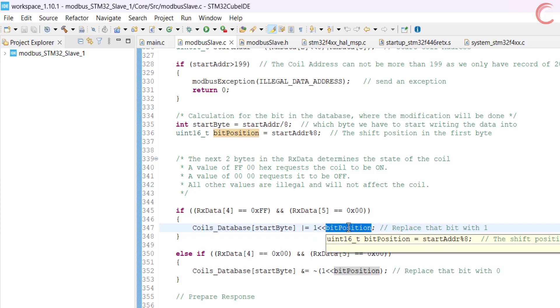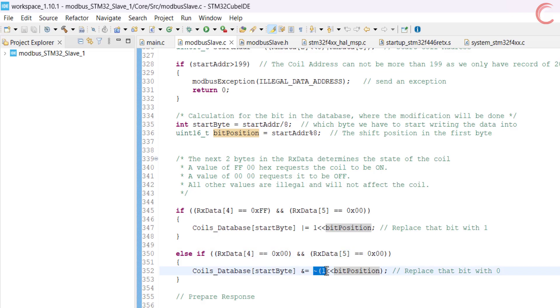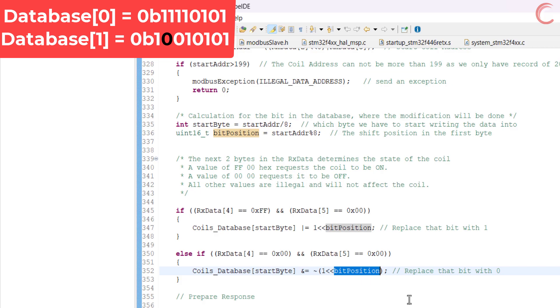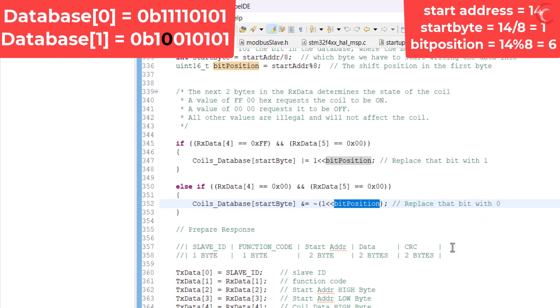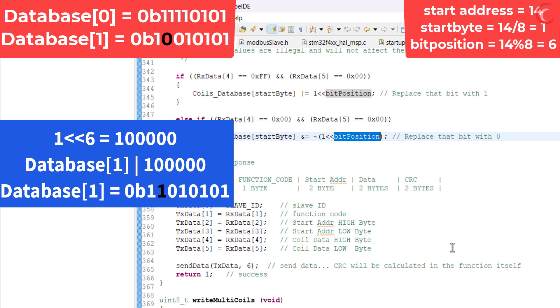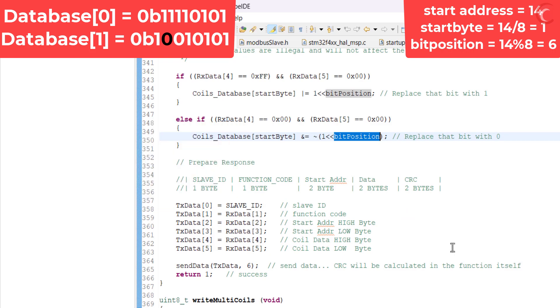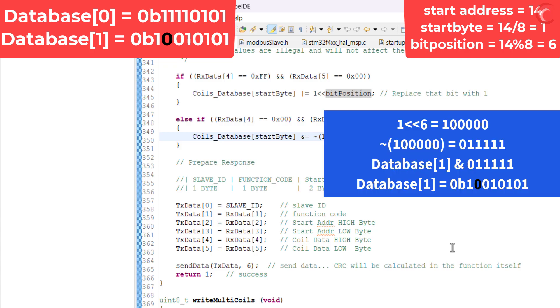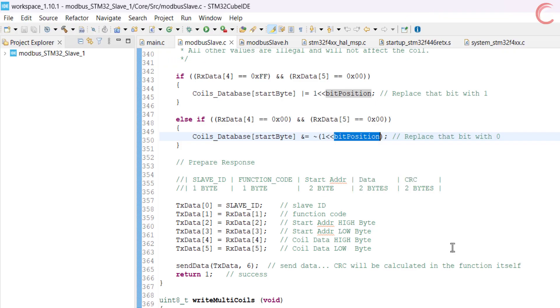So we will add a 1 to the bit position in the start byte. Similarly, if the 2 bytes are both 0s, we will add a 0 to the bit position. For example, if the master wants to write a 1 to the 14th coil, the start byte is 1 and the bit position is 6, so we will shift the 1 by 6 places to the left and OR the data with the start byte. If the master wants to write a 0 to the 14th coil, we will shift a 1 to the left by 6 places, negate the entire data, and perform the AND operation. This logic will remain the same even in the case of multiple coils.